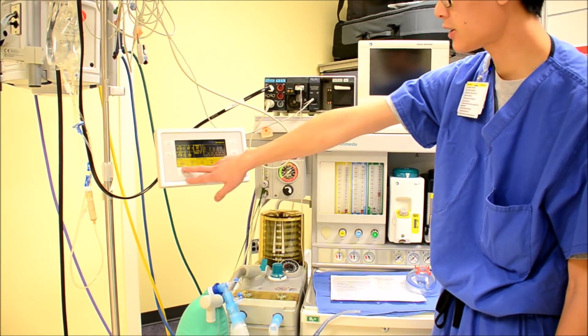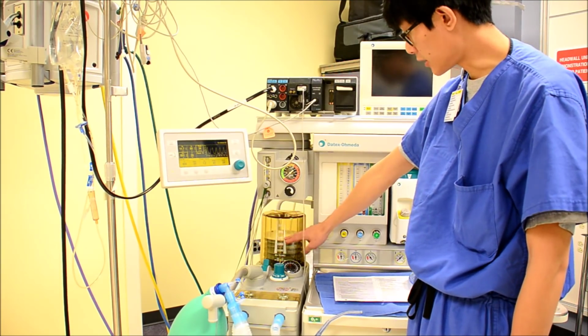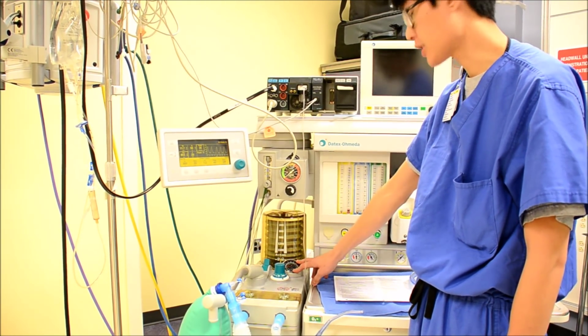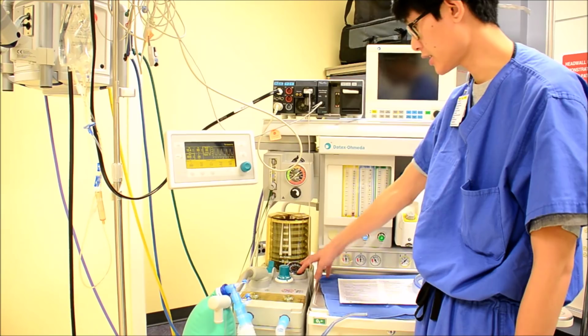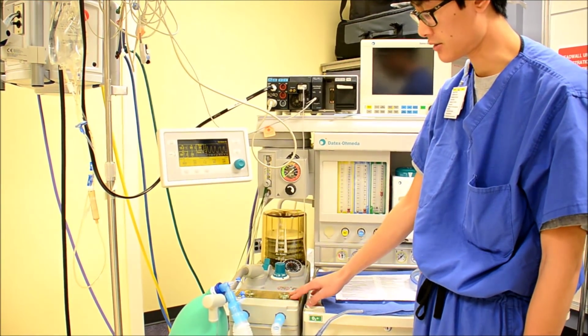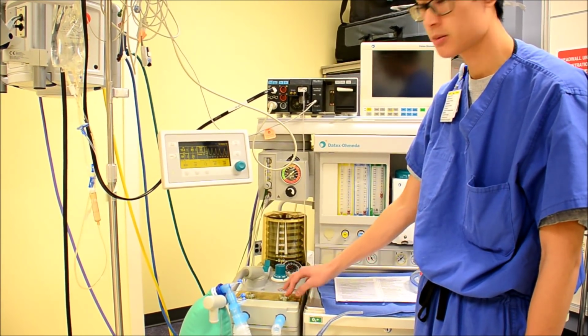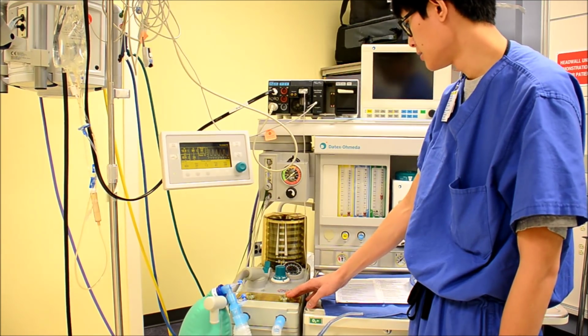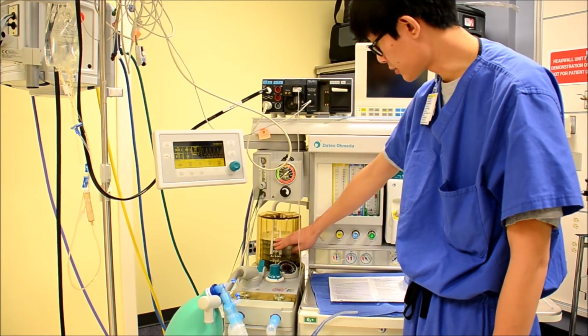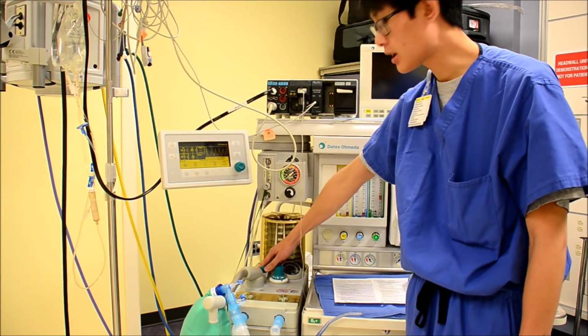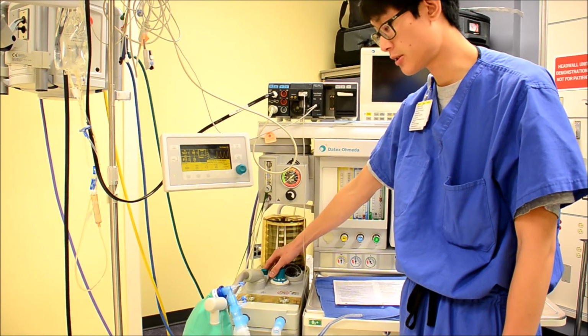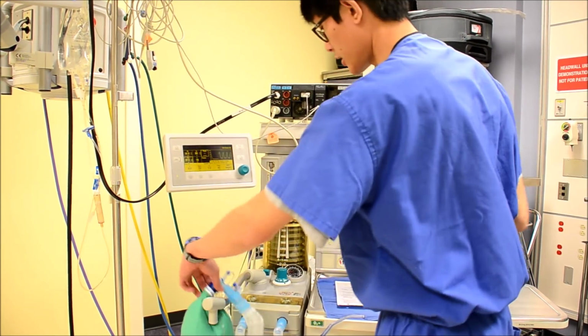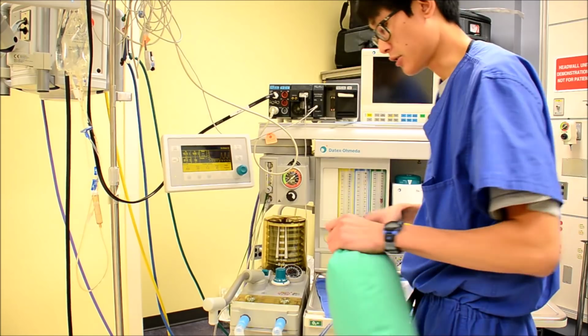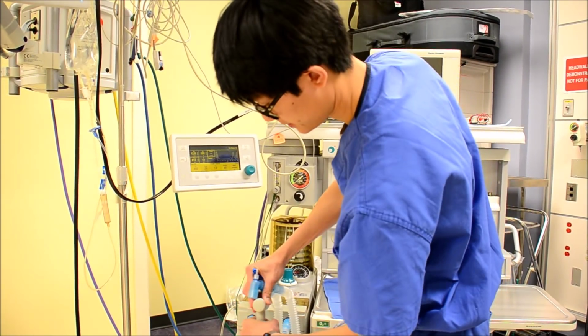So I've checked my tidal volume. Tidal volume on the bellows is reached. The pressure is reaching down to 0 on my pressure gauge, and inspiratory and expiratory valves are free and moving appropriately. So usually wait till the bellows get to the top, and then switch your mode to bag mode, and we're going to make sure that we can actually feel a breath if we deliver.